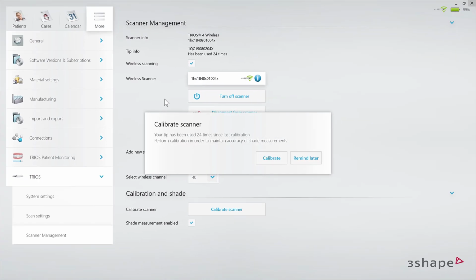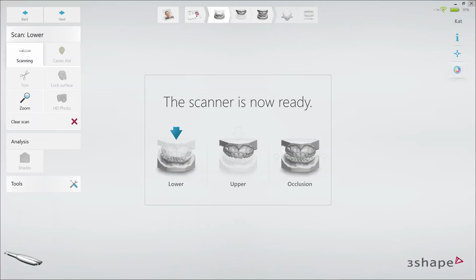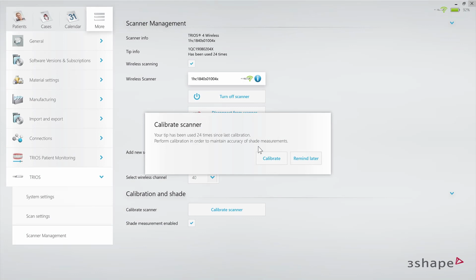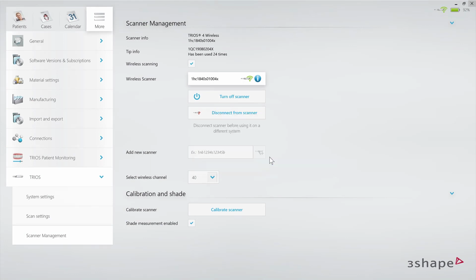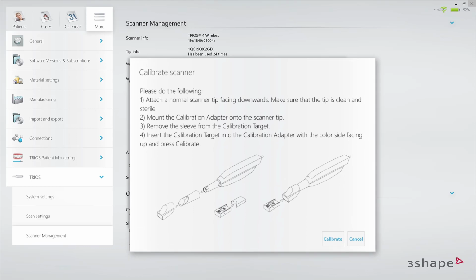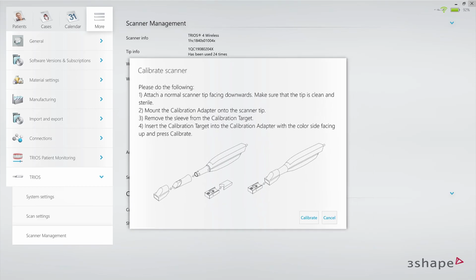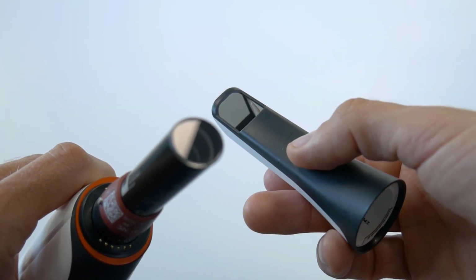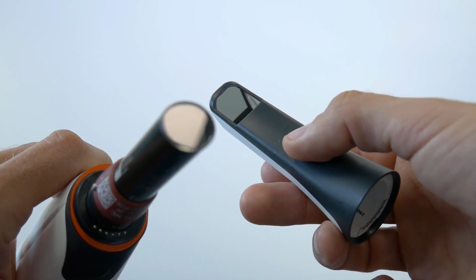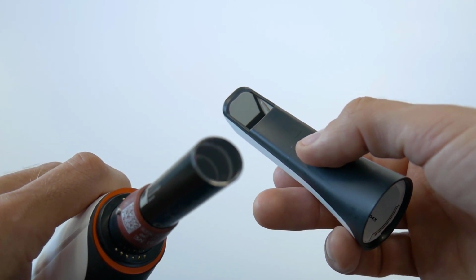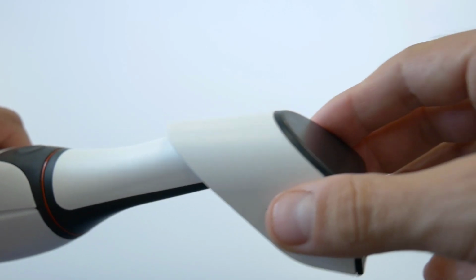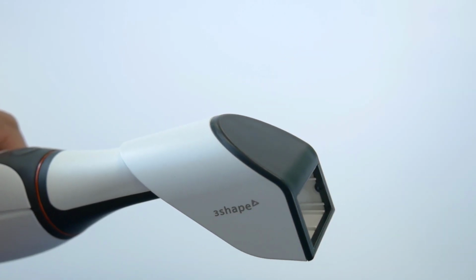There are three ways of initiating calibration. You can do this from the calibration pop-out, from the settings page, or the Tools tab on the scan page. Regardless of choice, click on the Calibrate Scanner button and follow the instructions in the pop-out. Make sure that the front glass of the scanner, as well as the tip mirror, are clean, sterile, and free of dust or scratches. Mount the calibration adapter onto the scanner tip.